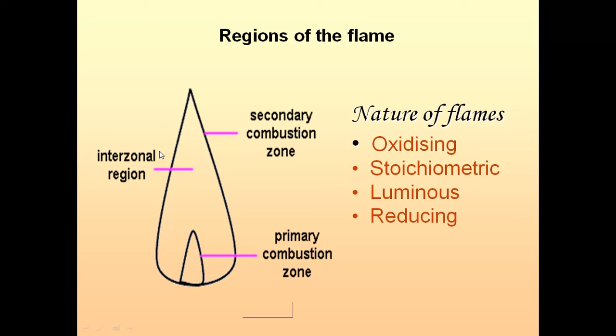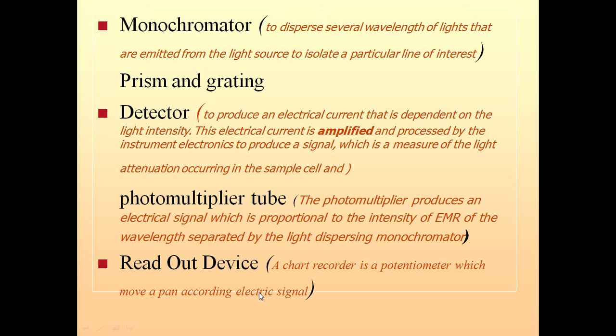Then we have the monochromator prism to disperse the wavelength of the light that is emitted from the light source to isolate a particular line of interest. This is the function of the monochromator. Then the detector produces the electric current that is dependent on the light intensity, and this current is amplified and processed by the instrumental electronics to produce a signal which is a measure of light attenuation occurring in the sample cell. And the photomultiplier tube basically produces an electric signal which is proportional to the intensity of electromagnetic radiations of the wavelength separated by the light dispersing monochromator. The readout device is basically the computer where we are getting the signal.